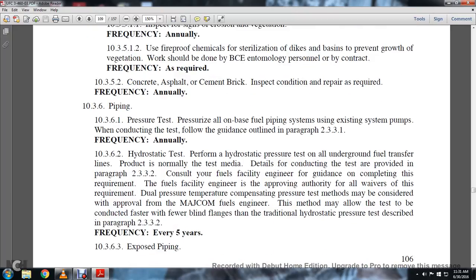10.3.6.2 Hydrostatic test. When the hydrostatic pressure test is for underground fuel transfer lines, the product is normally the test media. Details and conditions of the test are provided in paragraph 2332. Consult your facility engineer for guidance in completing this requirement. The fuel facility engineer is the approving authority for all waivers of the requirement.